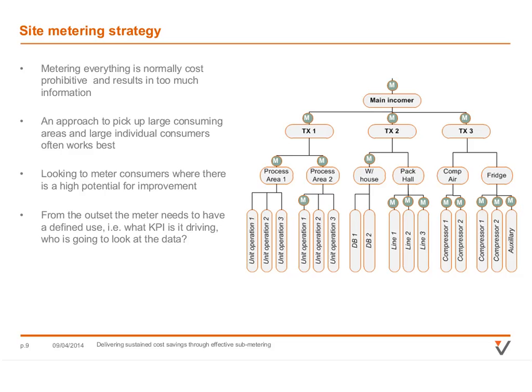I would probably always pick up the transformer level on the low voltage side, so that I can quickly work out which supplies might be affected if there's big deterioration. Then I'd be looking at the main culprits, maybe the whole warehouse if I can do it, and then going down to an individual air compressor or refrigeration compressor, or a big pump set, or a large process area like a slicing hall or bakery hall, picking up the main supplies for that.